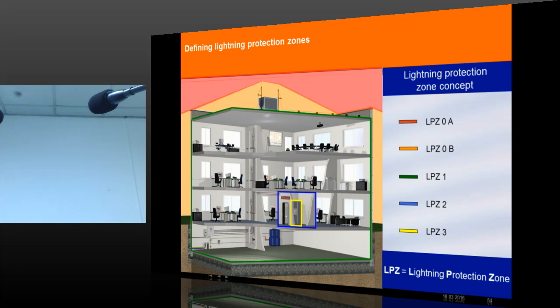So, in order to ensure that, you imagine you have a big air circuit breaker or an MCCB, which can withstand a higher impulse voltage. That is one condition in a building. The other condition is you have a very sensitive electronic equipment. So, the building is divided into various zones to ensure that the place where you are installing an MCCB, the same may be a PC, cannot be installed. So, you need to have different zones, and basically every zone boundary means an equipotentialization and a reduction of conducted and transmitted radiated surges.